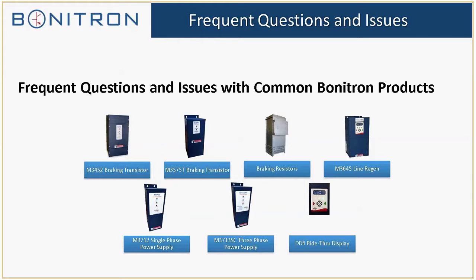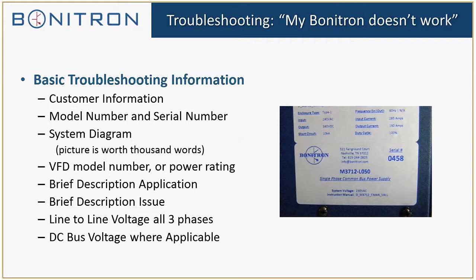So basically, I'm the tech support here. I will get a call or an email and have to respond to the very usual question of, "Hey, my Bonitron doesn't work." You start with the basic information; serial number and model number of the unit is very helpful. The next most helpful thing is, of course, the system drawing. It helps so much to see how our units are connected up to the drive and everything else. In this case, a picture is literally worth 1,000 words, and it helps us start troubleshooting. Even though most of our units require very few connections with the drive, it's still worth having that drawing, so that the customer and I are on the same page.